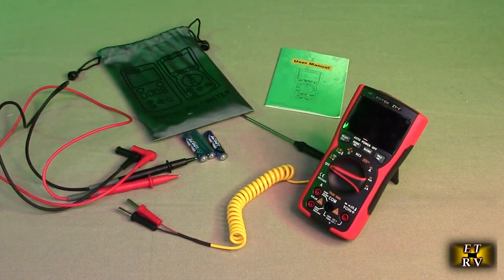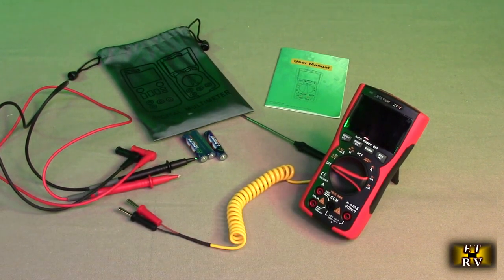This has a lot of unique functions. It has a V.F.C function, which includes a built-in low-pass filter to filter some of the clutter when you're measuring DC and AC. That's on the front end of the device, so that's something that helps you get a more accurate reading. This will measure AC or DC in millivolts or voltage, up to 10 amps of current.